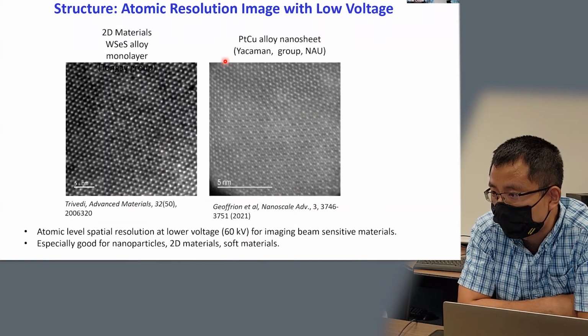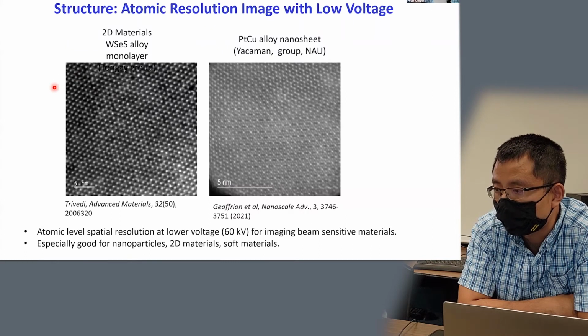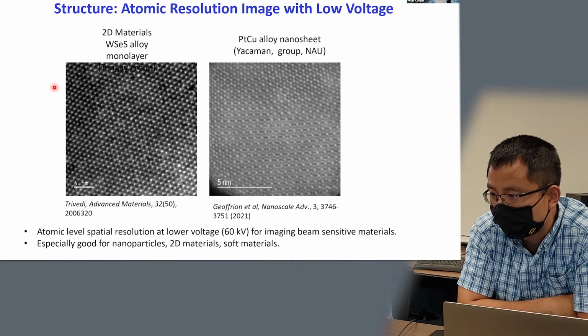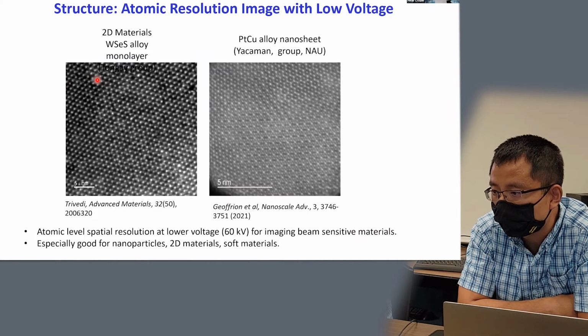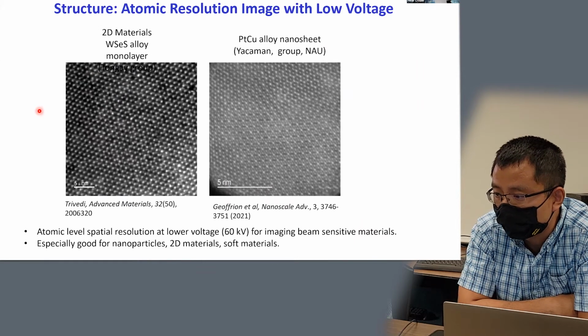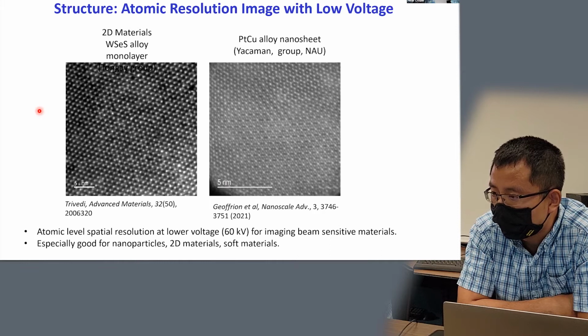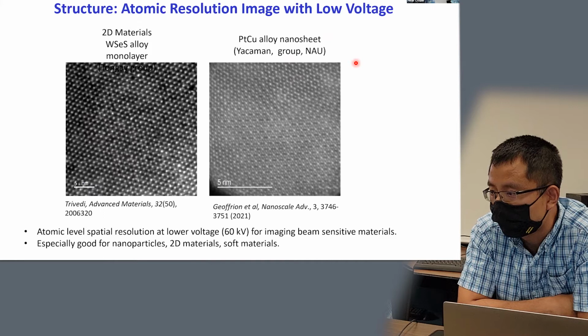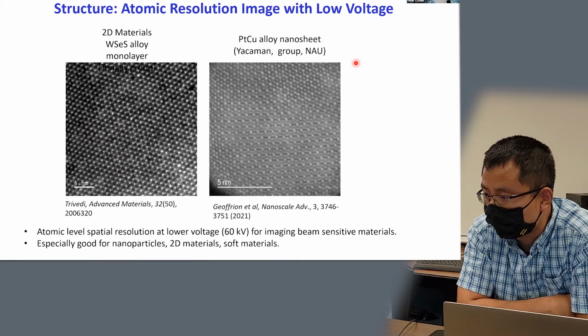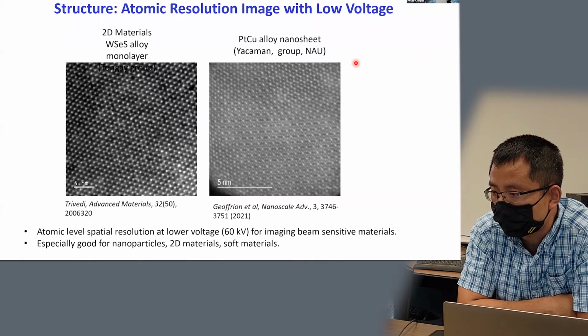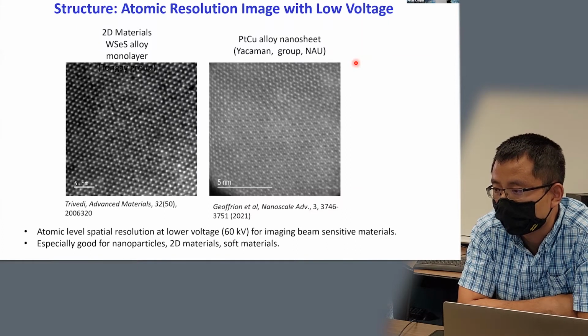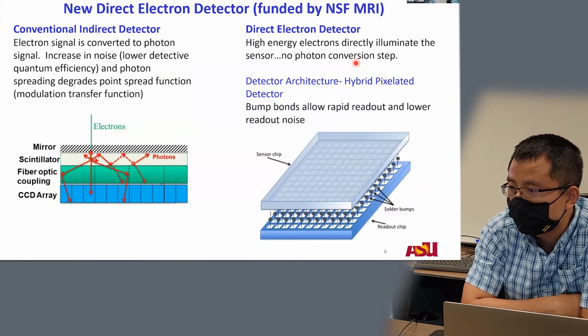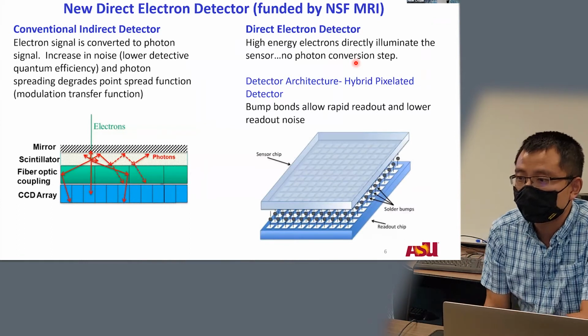Here are some examples where we use the low electron beam voltage to image atomic structure. The material on the left is a 2D tungsten, selenium, sulfur Janus monolayer from a photonics group at ASU. And the right image shows a platinum and copper alloy nanosheet, sampled from a Northern Arizona University group. These images show that the microscope offers really good spatial resolution. Now, Peter Crozier will introduce the new detector.